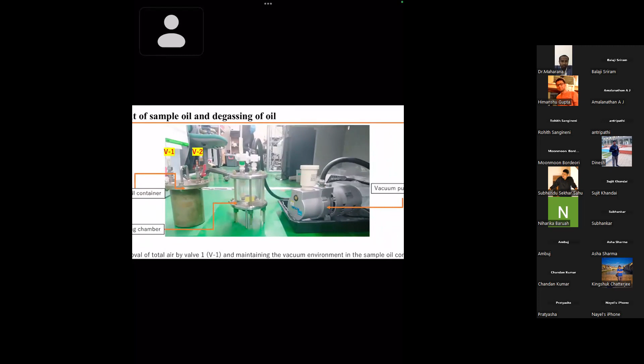So before carrying out the experiment, we need to take into consideration the moisture in the oil. For that, we need to dry the oil and degas it. There is a vacuum pump. This is a very basic mechanism. We suck the oil from the sample container and put it in a degassing chamber. V1 and V2 are the two valves. One will vacuum the container, and the other will take out the degassed oil. That is how we confirm that it is gas free and that the moisture is very much lower. We cannot say moisture free, but we can calculate that moisture. We can remove the added moisture which previously came with the oil from the company.